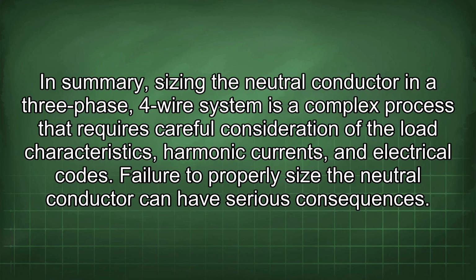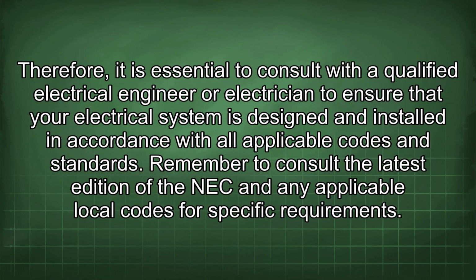In summary, sizing the neutral conductor in a three-phase, four-wire system is a complex process that requires careful consideration of the load characteristics, harmonic currents, and electrical codes. Failure to properly size the neutral conductor can have serious consequences. Therefore, it is essential to consult with a qualified electrical engineer or electrician to ensure that your electrical system is designed and installed in accordance with all applicable codes and standards.